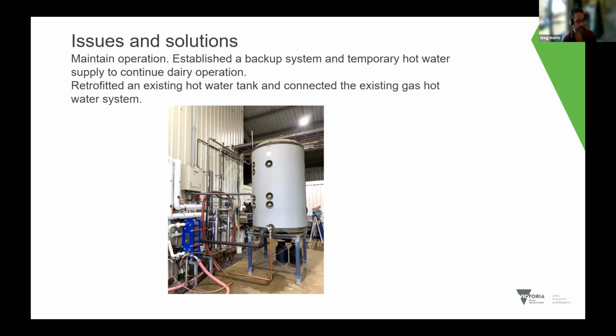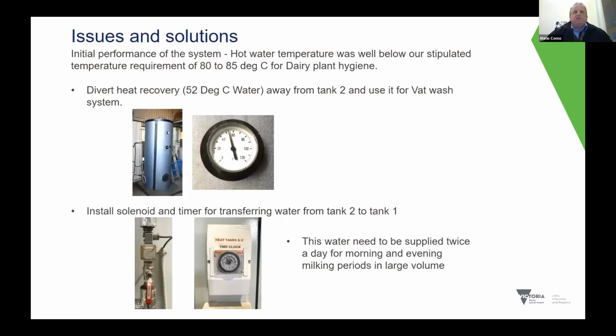A couple of the key points, and one of the main ones, is what we needed to do here was to establish a backup hot water system. We weren't sure how long the install was going to take. Obviously, being a dairy farm, we operate all year round, so we had to make sure we had the correct volume, and not only volume but temperature, of water to maintain that hygiene system while we continued the milking. We did this just utilising a heat recovery tank that we had spare, and made use of the instant gas system that originally supplied the electric hot water services. And look, it really worked well. It maintained that temperature very well. Mario, I think we're up to you, mate.